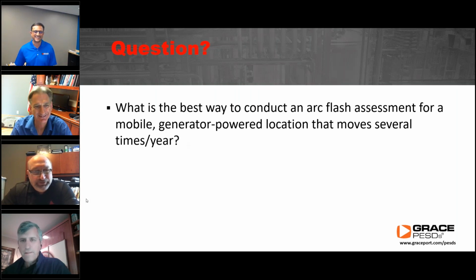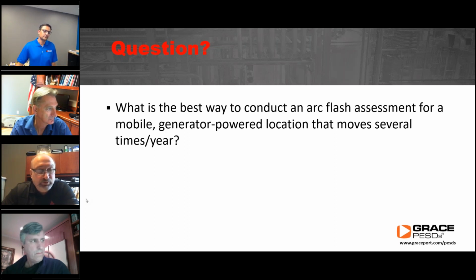So again, it's very interesting how these questions move around. So if you have a mobile generator powered location, and if that's a fixed system, the same generator moving from location to location, your source of fault current hasn't changed. Now the challenge will be the temporary power, because I'm assuming this is temporary power generation and distribution. The length of your conductors to your panel boards will change.